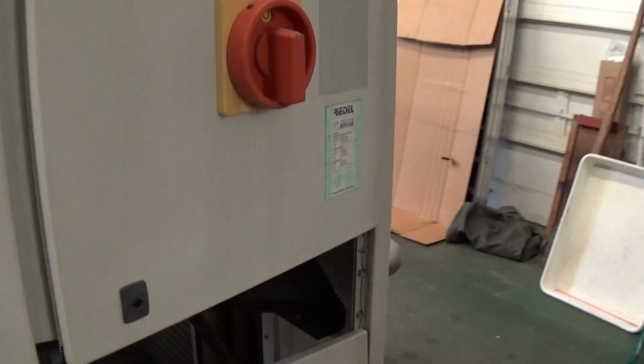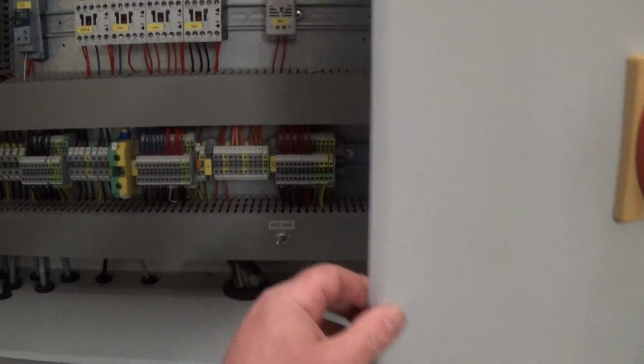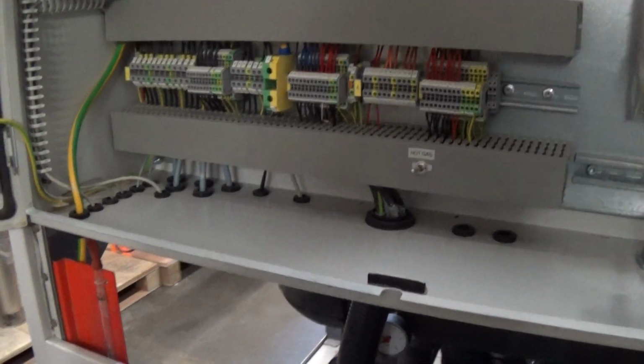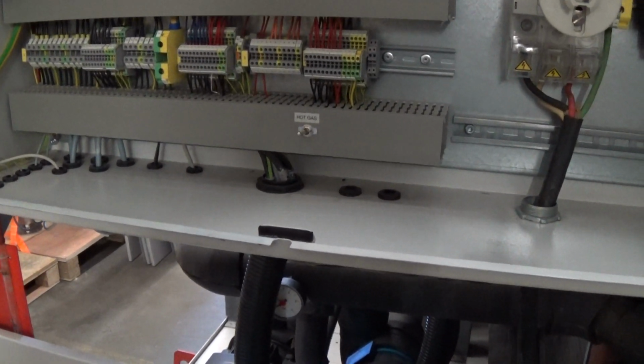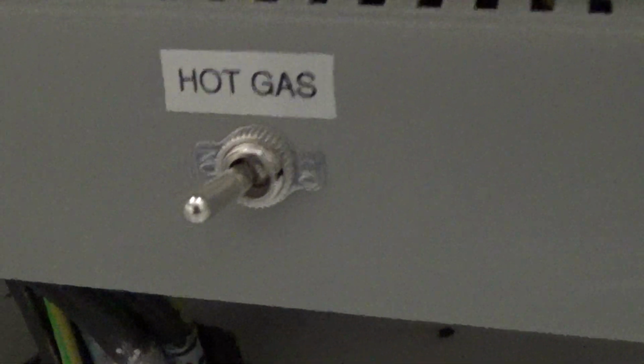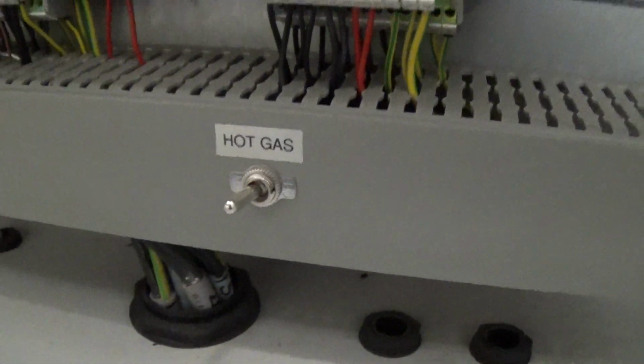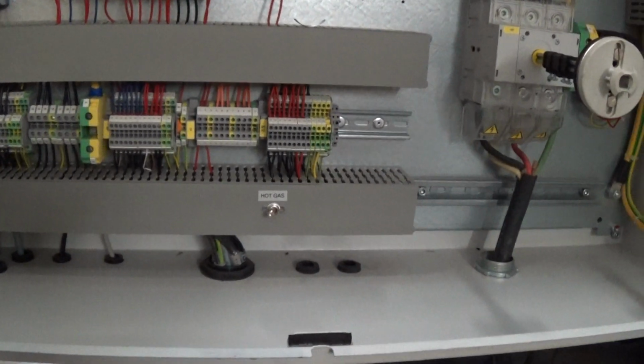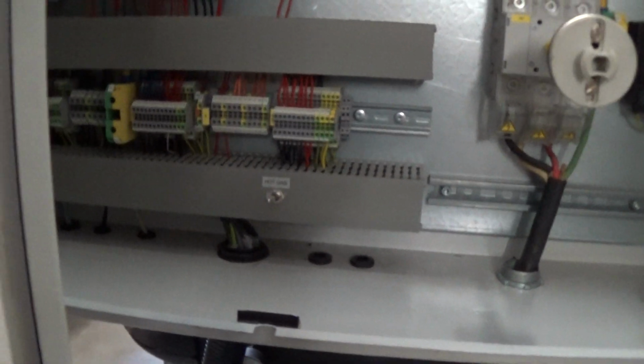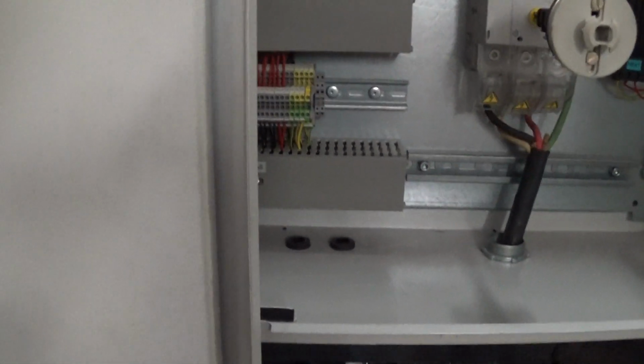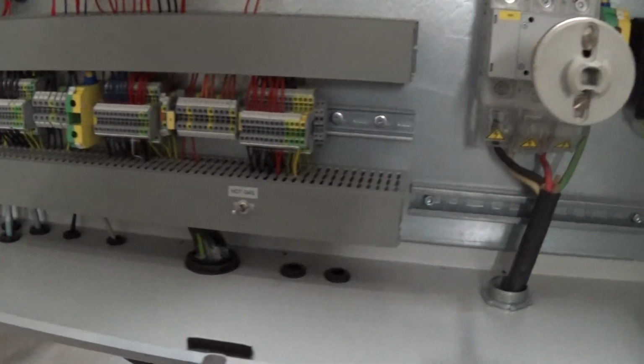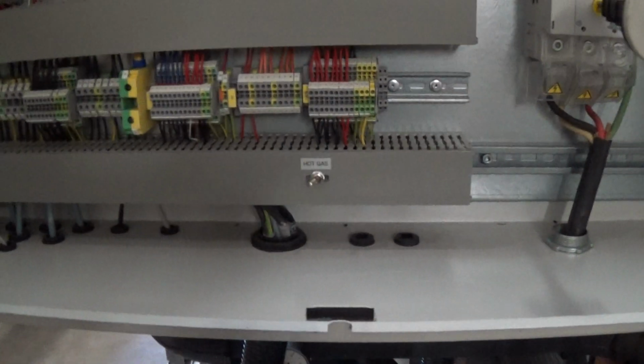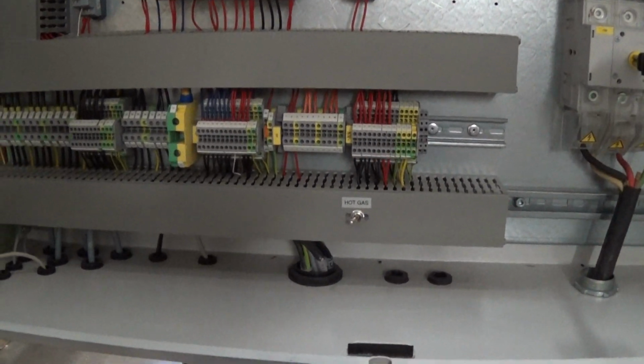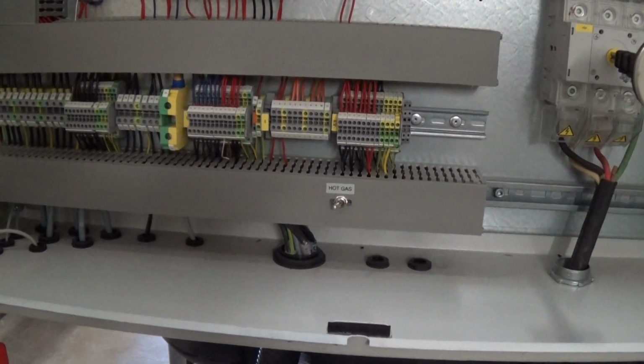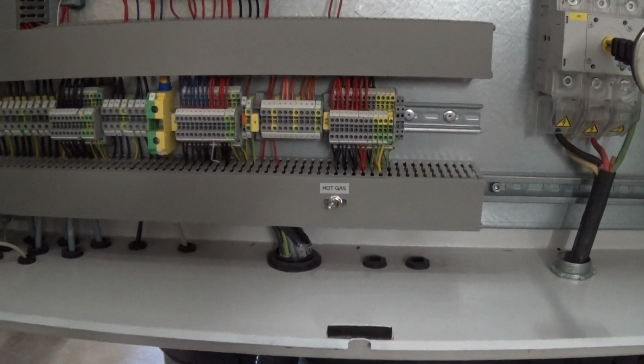In some cases, depending on temperature and certain applications, the hot gas bypass might be on for too long, which is what we find as chiller suppliers constantly modifying and working on chillers for different applications. So we like to put in an actual on-off switch, which we did here, to turn the hot gas feature on or off. An example of why you would want to turn it off is if you realize that the compressor never turns off, you always hear the chiller running, in which case you'll want to turn the hot gas off, and you may find it operating in a better scenario for you. The hot gas is nice for certain conditions in that it helps stabilize your temperature and maybe keep one of the compressors running for a half hour or hour or two while it's holding and keeping a particular set point temperature steady.